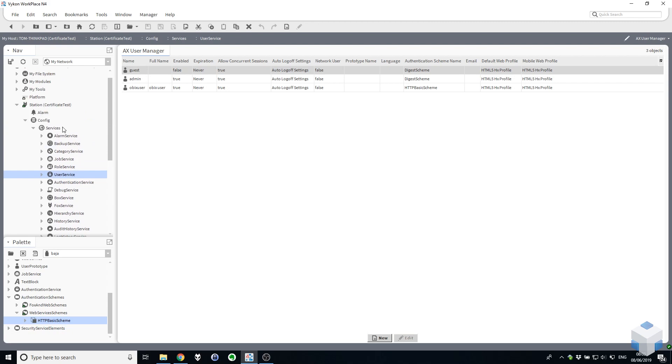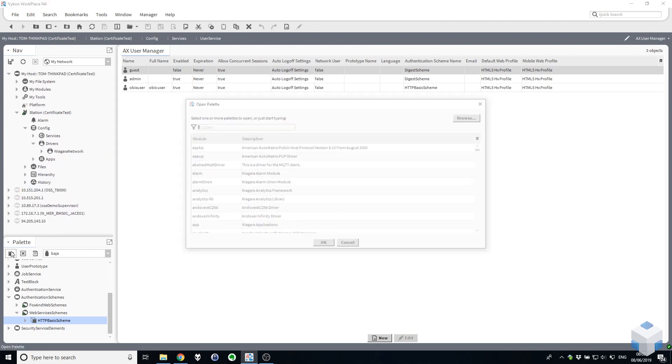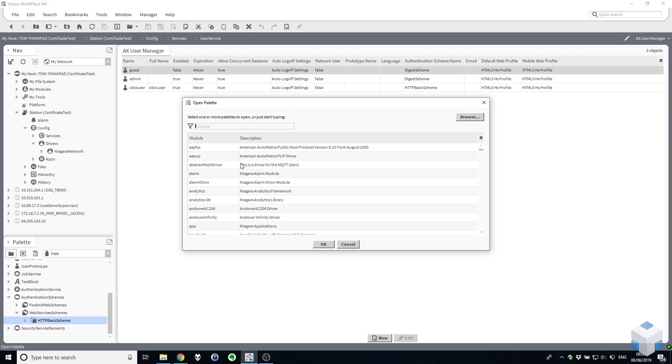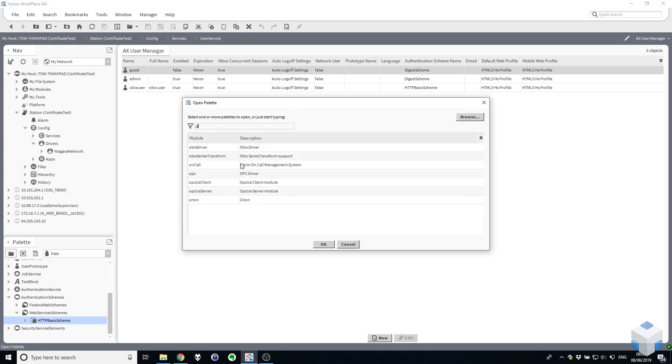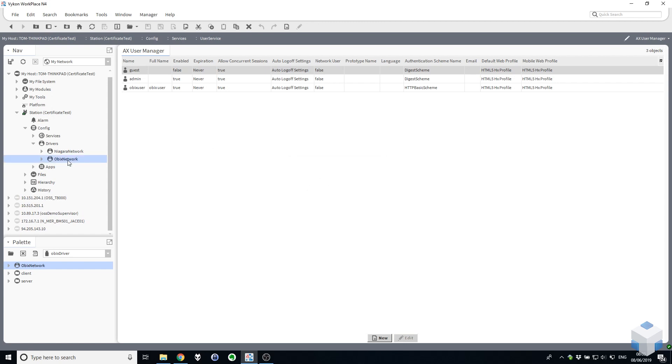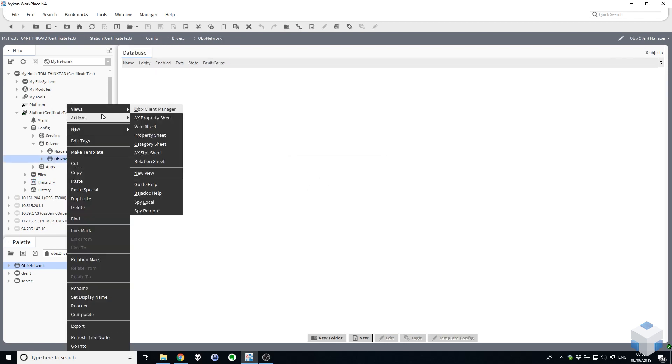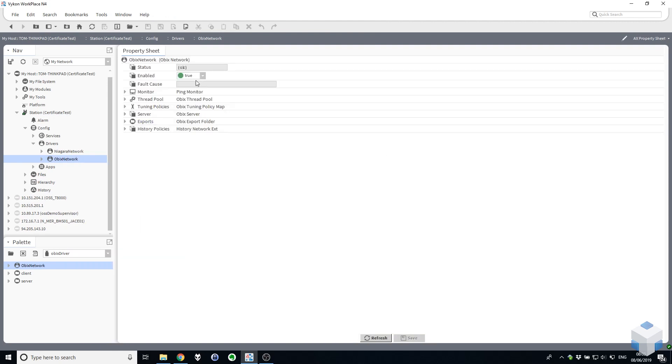The next thing we need to do is close down Services and expand Drivers and in our palette here search for OBIX and you'll see the OBIX driver. So grab yourself an OBIX network, drag it onto the drivers. Just a quick check of the property sheet, make sure it's enabled and it is. So at this point your Niagara system is enabled and ready to receive OBIX requests for data from OBIX clients.